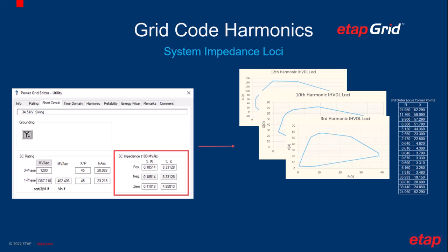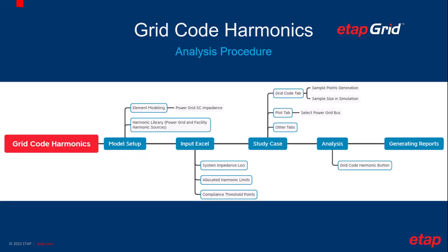Now, with this understanding, we are able to do the analysis and compare against the harmonic limits. Here is a chart showing the steps of performing a grid code harmonic analysis. Compared to many other studies you might have been familiar with in ETAP, the main difference here is the setup of the system impedance loci and the allocated harmonic limits. This information is set by an input Excel. Now let's see a demo using ETAP.